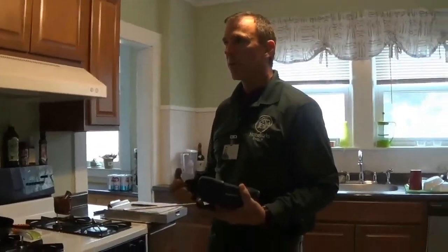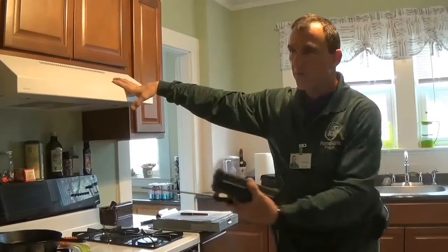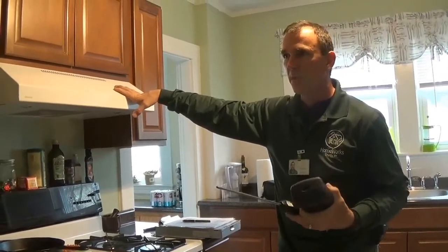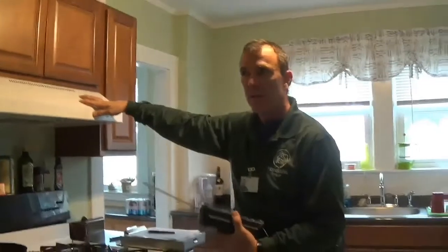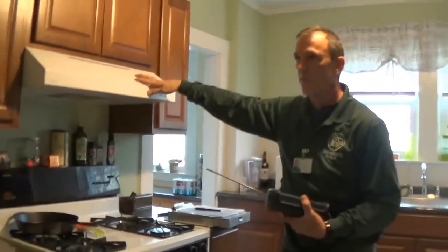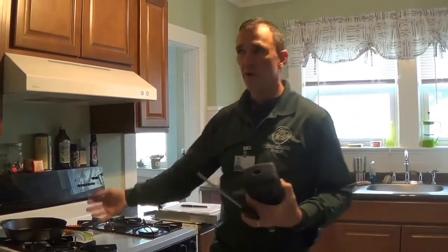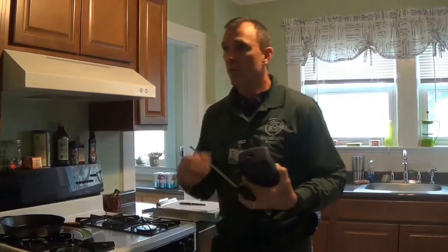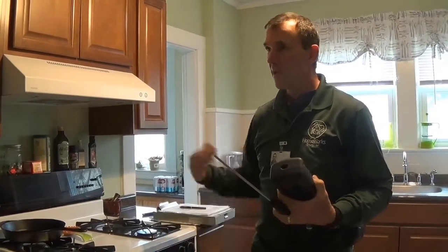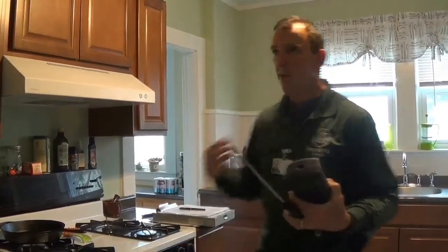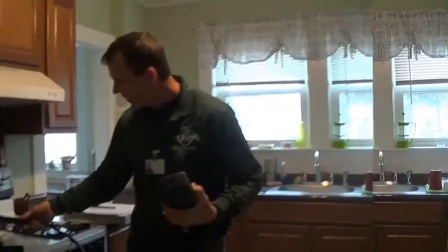We want to measure what the carbon monoxide is after it's had a chance to get to steady state, which is when you preheat it. I poked that in there for a second and it was above 100 parts per million, and then it went down. So I'm hoping that this oven ultimately will have a number that's less than 100 parts per million. For Mass Save, if it's between 100 and 300 in here, then we write a disclosure that says it's not a roadblock to work, but you want to get your oven cleaned and tuned to get that carbon monoxide in the exhaust as low as it can be. And then the ambient is going to be as low as it can be, and it might actually be 0 out here. I'm going to go ahead and try again.